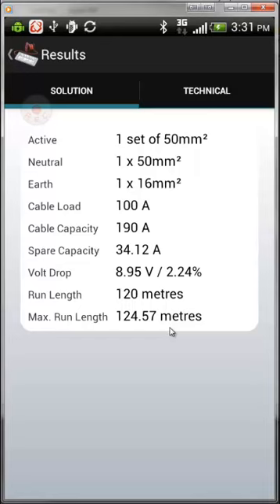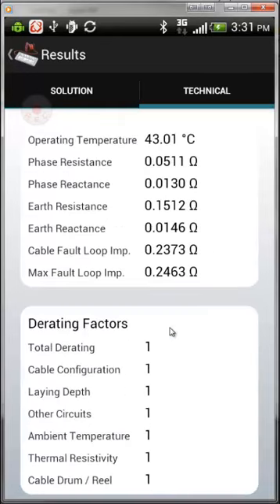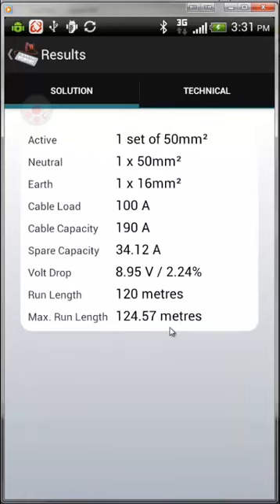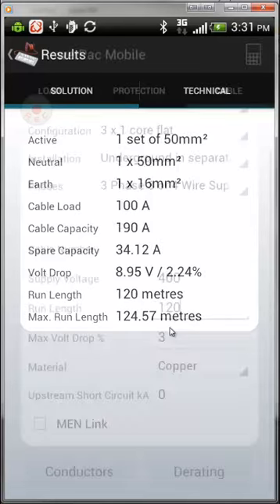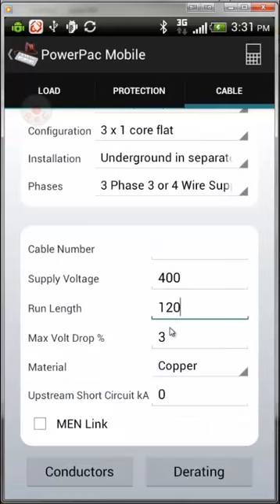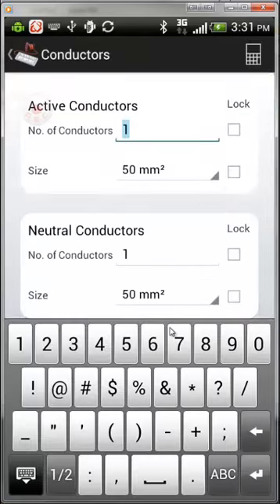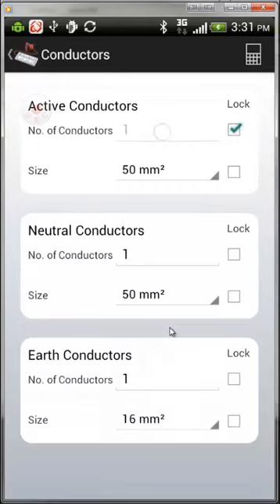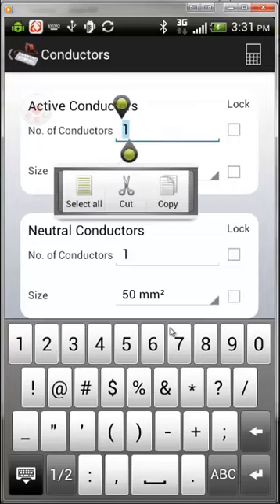Now hit the Calculate button. The software will run the calculation — in this case we need a set of 50mm² cables. More technical information is available based on earth fault loop resistance and reactance, and it will tell you how far you can run this cable. You can go back and make any changes, such as locking conductors in place, and then re-run the calculation.